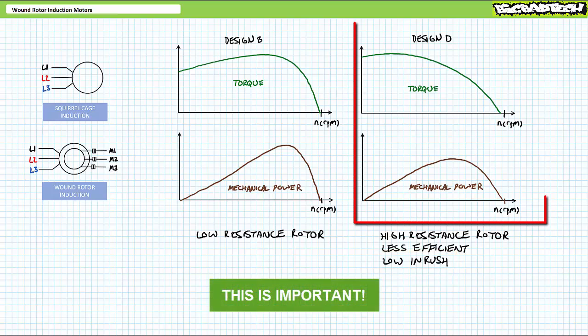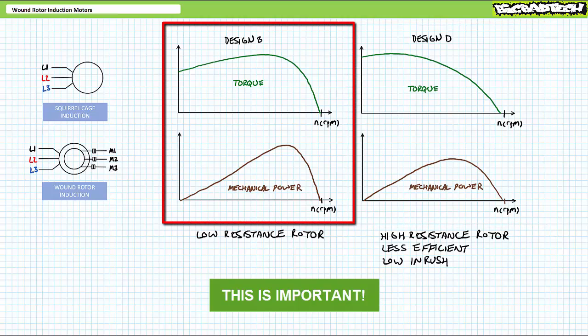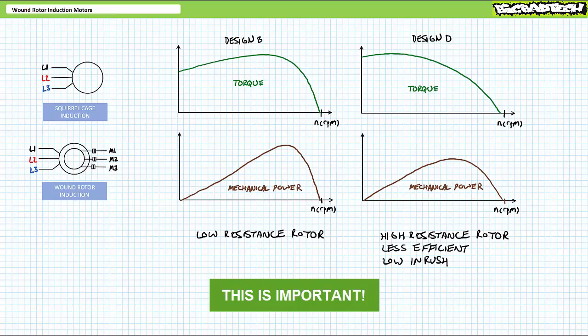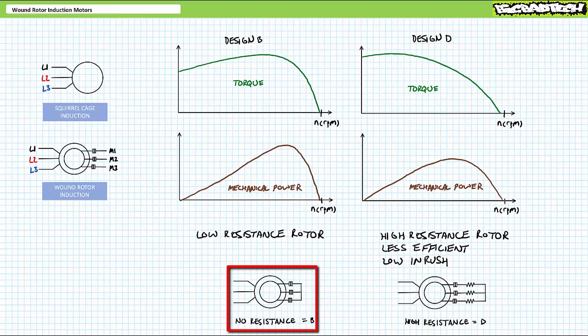Wouldn't it be great if you could have the high torque starting ability and low inrush current demand of a high resistance design D rotor, and when the load is actually moving, switch back over to a low resistance design B rotor such that it operates more efficiently at higher rotational speed? Wound rotor induction motors allow this duality. This would be impossible for a squirrel cage induction motor lacking access to the rotor. However, wound rotor induction motors with slip rings on the rotor permit a degree of customization to the rotor circuit, thus a degree of flexibility to meet the needs of a particular application. You want design B operation? Don't add resistance. You want design D operation? Add resistance. Additionally, a primitive form of variable speed operation can be accomplished by varying the resistance of the wound rotor induction motor rotor circuit while in operation.